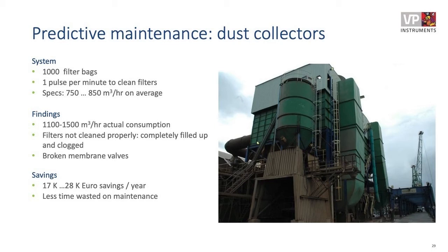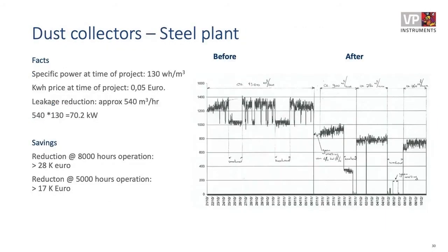So let's take a look at the data. Here you see the before period and the after period. You can clearly see that after repairs, the air consumption went down significantly. And here are some saving calculations. They had a specific power at that moment of the compressors. In this case, it's not in kilowatt per cubic meter per minute, but in watt hour per cubic meter. This was a way for them to calculate the approximate costs of compressed air per cubic meter. Then they could calculate the reduction at 8,000 hours of operation and 5,000 hours of operation. And you see these are significant amounts.